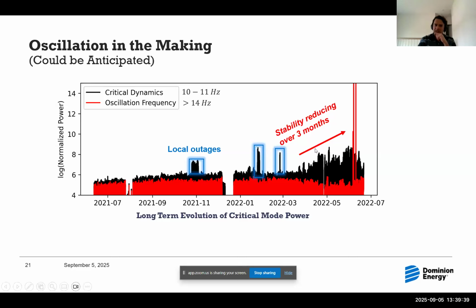I'm plotting the signal power in the 10 to 11 hertz range, along with the voltage magnitude signal power in the 14 to 15 hertz range. This is 1 year of data. The black is the signal power, or the critical dynamics behind the oscillation. Whenever we took local outages in that region, you'll see an increased power, or a relatively less stable 10 to 11 hertz mode, which is expected. This means we could have gathered these clues in the past - whenever there were outages, the 10 to 11 hertz mode becomes relatively less stable.